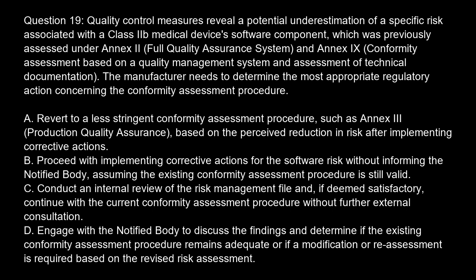Option A. Revert to a less stringent conformity assessment procedure, such as Annex III, Production Quality Assurance, based on the perceived reduction in risk after implementing corrective actions. Option B. Proceed with implementing corrective actions for the software risk without informing the notified body, assuming the existing conformity assessment procedure is still valid. Option C. Conduct an internal review of the risk management file, and if deemed satisfactory, continue with the current conformity assessment procedure without further external consultation. Option D. Engage with the notified body to discuss the findings and determine if the existing conformity assessment procedure remains adequate or if a modification or reassessment is required based on the revised risk assessment.